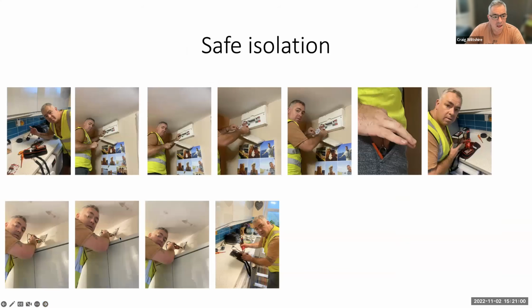Safe isolation: circuit identification, knock off, lock off, warning tag, key in pocket, prove the GS38 approved voltage indicator. I don't want to see this done with a multifunction tester, guys. It's got to be one of these. Prove it on a proving unit or a known source. So prove the tester before, then line to neutral, line to earth, neutral to earth, and reprove the tester. Happy days. So here are safe isolation pictures from start to finish in a nice little sequence.